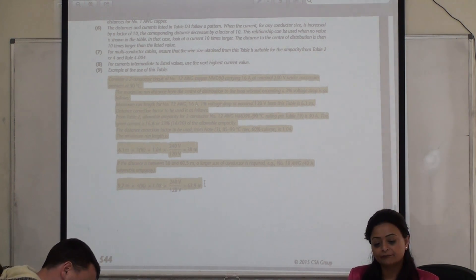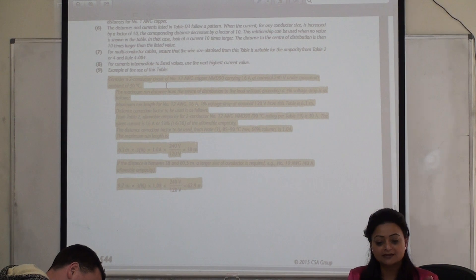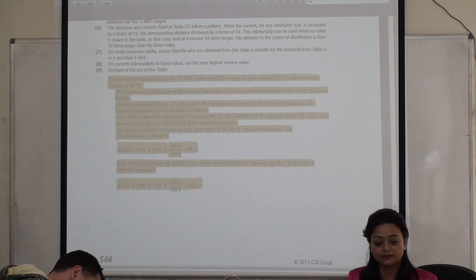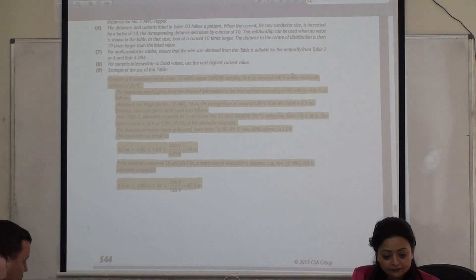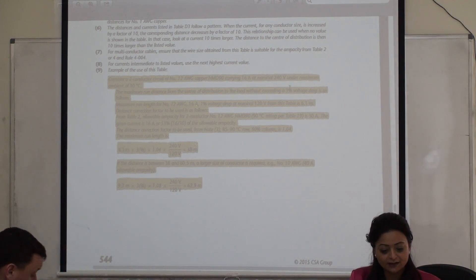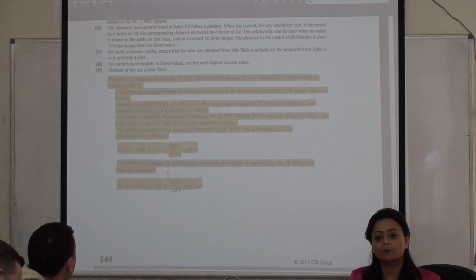In this example on Note 9, he's given you 16 amps of current, voltage is 240 — not 120 — and the drop allowed is 3%. He's shown you the story of what to do to find your answer. I want you to copy the formula I'm going to write down on the board.